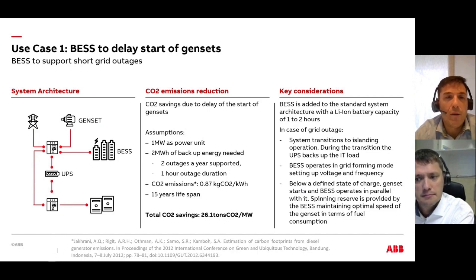And we aim here, we have calculated, you have here the assumptions that we have considered: 1 megawatt as power unit, 2 megawatt hours of energy needed. We consider 2 outages a year and 1 hour of those outages as a duration. So we get CO2 savings of 26.1 tons per megawatt.